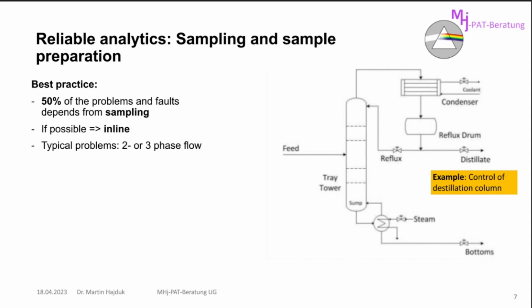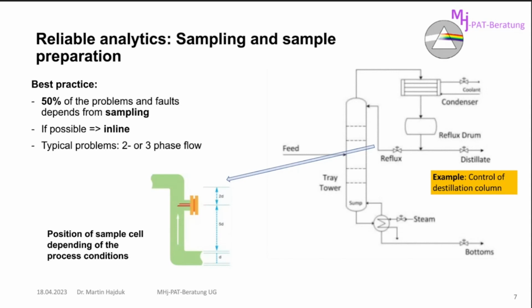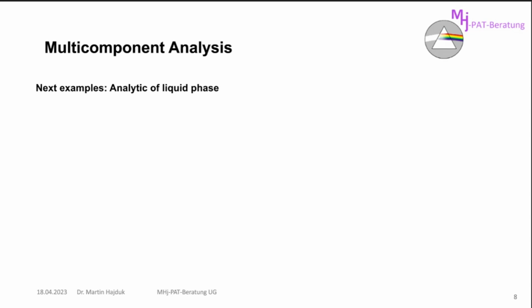But what kind of problems can we have here? Possibly we have a 2 or 3 phase flow. We have organic liquid. Sometimes we have still, before starting, water inside. Then we have also water bubbles, possible water bubbles inside. And if the temperature is not low enough, we have problems with gas bubbles. So we can use here, or normally we should use, a sample cell in the vertical tubing, and we also have a look at what we can do before the sample cells, so that water drops and particles and gas bubbles don't disturb our process. I have to reduce to the liquid phase.